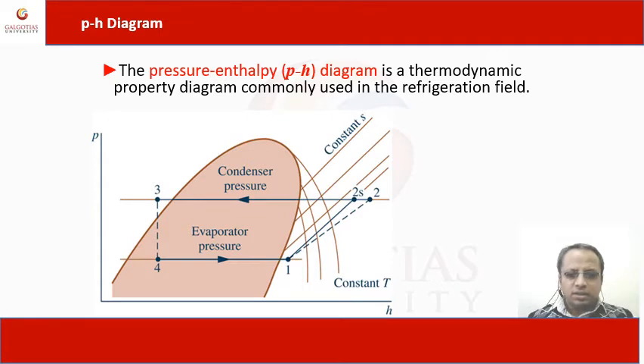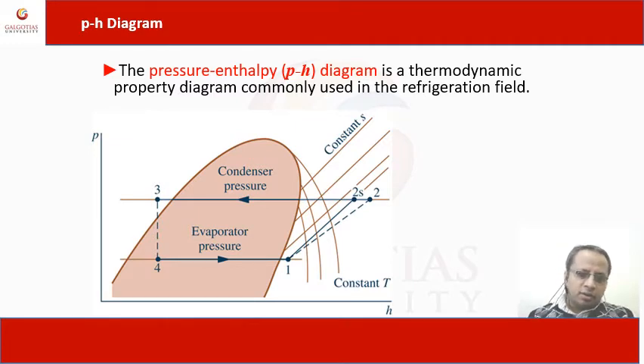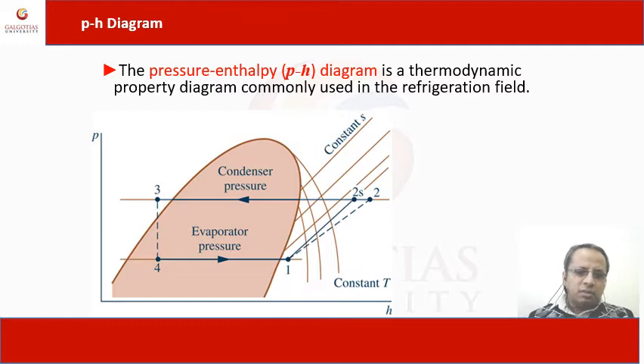In a domestic refrigerator, the working refrigerant is R134A. The higher pressure exists after the compressor, because the compressor converts the refrigerant into higher pressure and high temperature. The high pressure of the VCR cycle is maintained after the compressor. According to the thermal property of R134A, which is used nowadays in air conditioning and domestic refrigerator systems, the higher pressure is maintained at about 7 to 8 bar, and in this condition, R134A achieves the superheated condition.